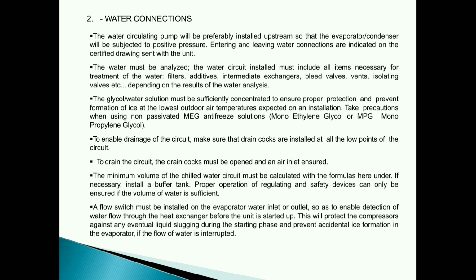1.2 Water connections. The water circulating pump will preferably be installed upstream so that the evaporator and condenser will be subjected to positive pressure. Entering and leaving water connections are indicated on the certified drawing sent with the unit. The water must be analyzed. The water circuit installed must include all items necessary for treatment of the water: filters, additives, intermediate exchangers, bleed valves, vents, isolating valves, etc., depending on the results of the water analysis.